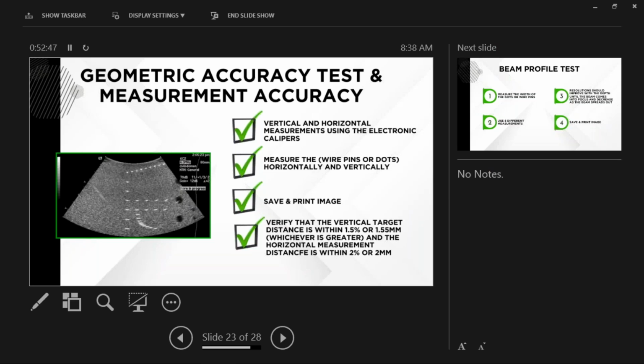The first thing I want to do is select the presets for the transducer. I want to adjust the depth and the focus to the max depth, and then I'm going to measure the depth with the electronic calipers with our wire dots in the particular system. So on your ultrasound phantom, I know it's tough to see, but afterwards you can come up and take a look.